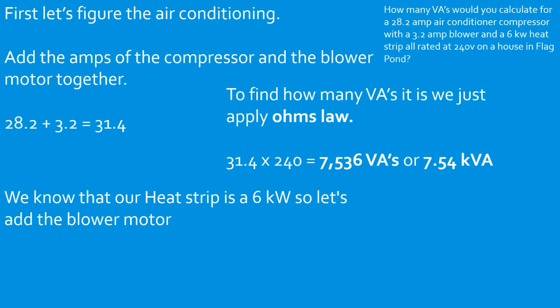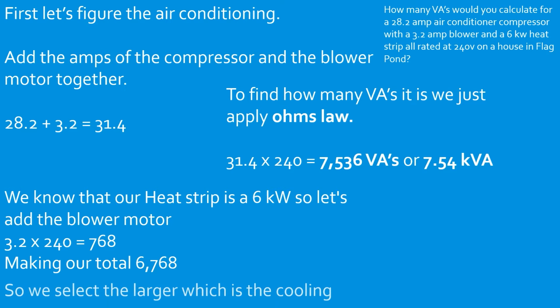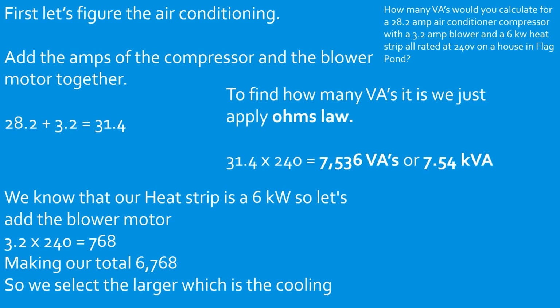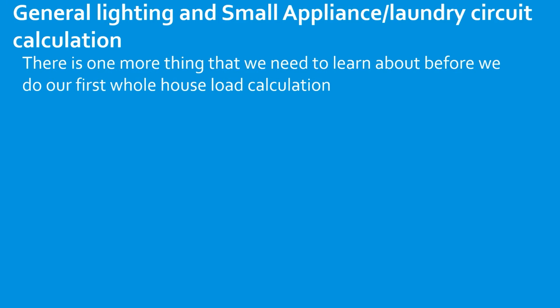We know that our heat strip is a 6 kW, so let's add the blower motor. So we just take our 3.2 amp blower motor and multiply it by 240 volts. That's going to give us 768 more VAs that we need to add. So we add that up, and that gives us a total of 6,768 VAs. And in this case, we're going to select the larger, which is the cooling, and we're going to select B. Great job.